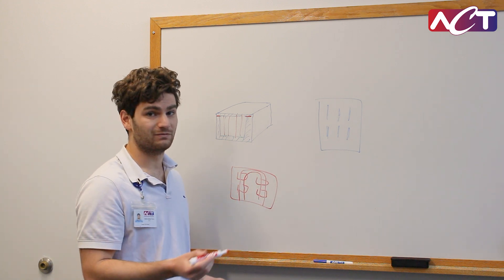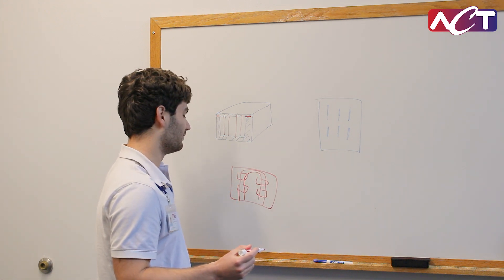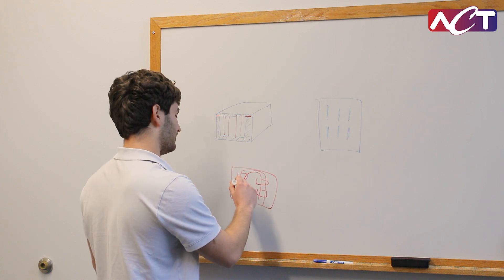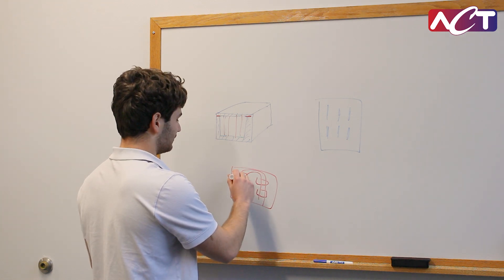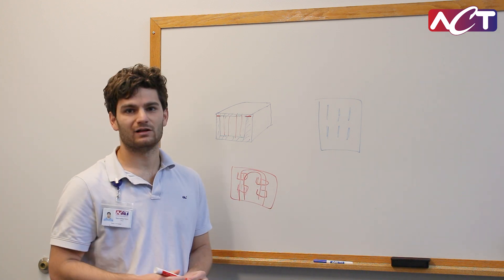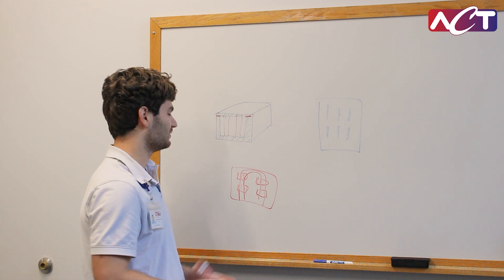This is something that would be very difficult, if not almost impossible, without vacuum brazing. But with vacuum brazing you can not only make this channel, but you can have finned regions here to increase your heat transfer directly under, while leaving the rest of the channel open to help lower pressure drop.